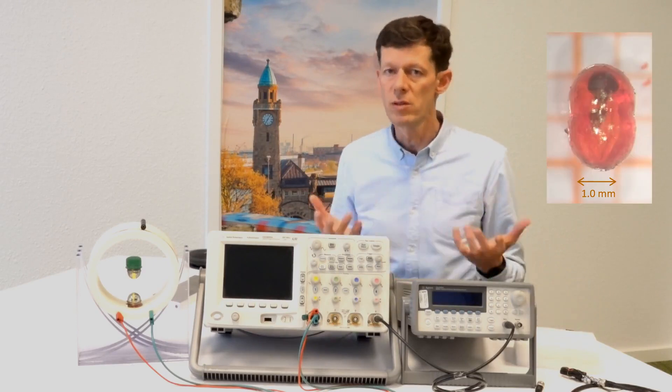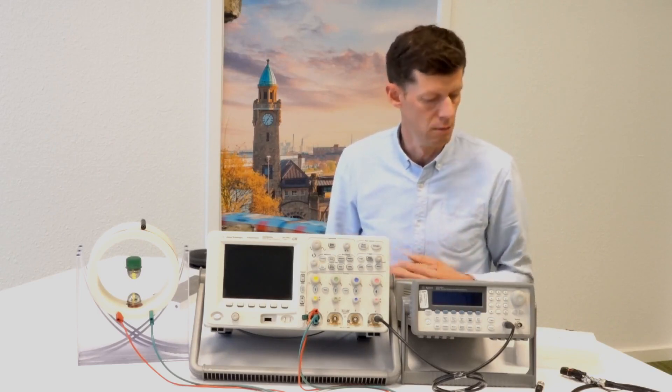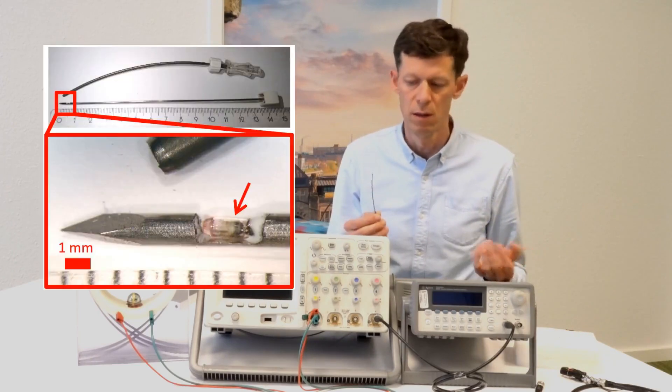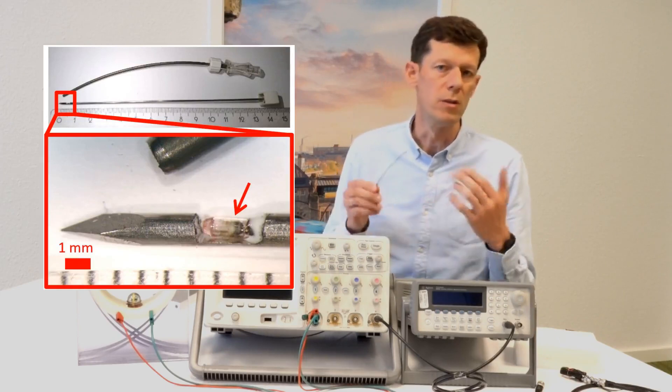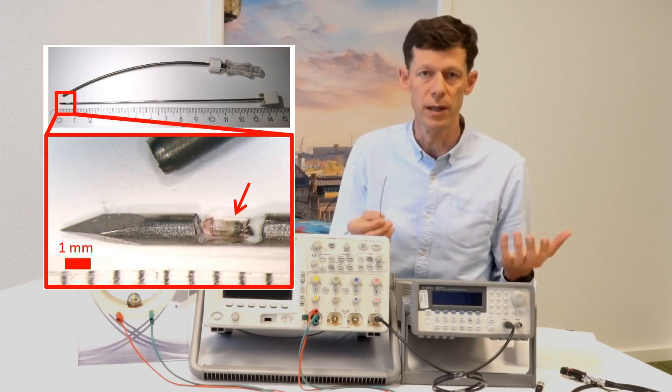Due to the small size, we can easily integrate these markers into small devices. For example, into a biopsy needle. Here we put a marker to the tip of the needle so we can track its position and full orientation remotely in real time.